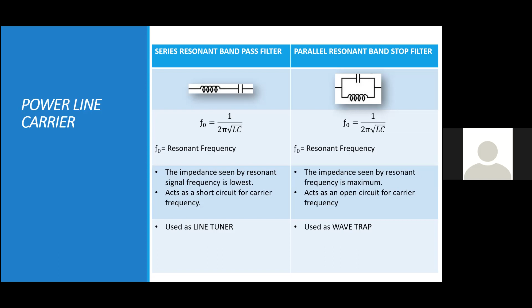As the name suggests, it's a band stop filter. At its resonant frequency, the impedance seen by the tuned frequency is maximum, so it acts as an open circuit. This facilitates that our carrier frequency doesn't go into the power system, but stays on the transmission line and doesn't enter the substation and cause interference.